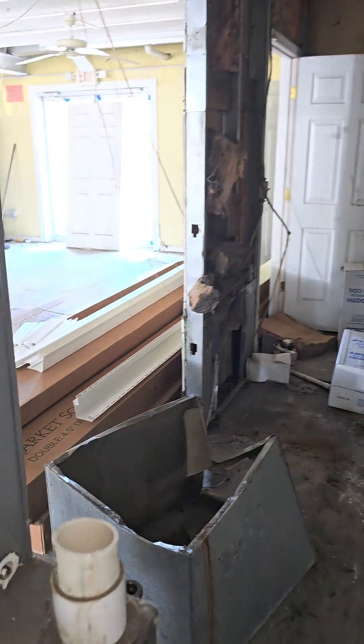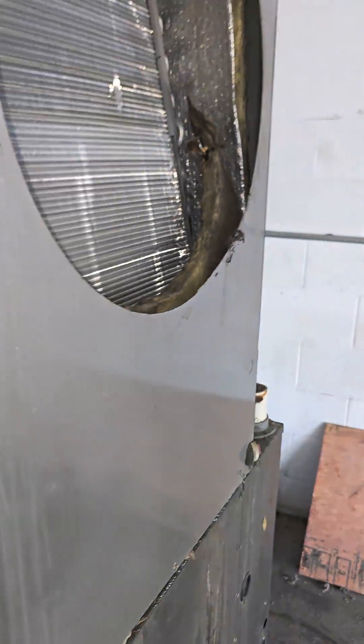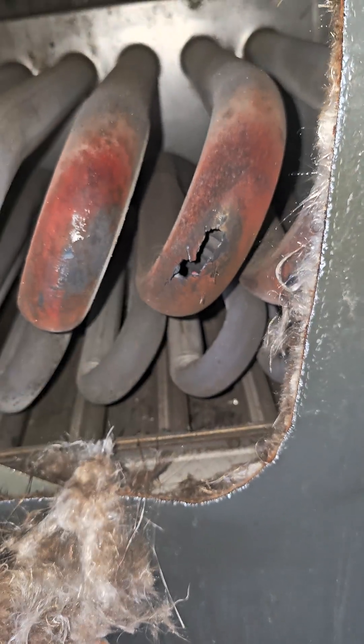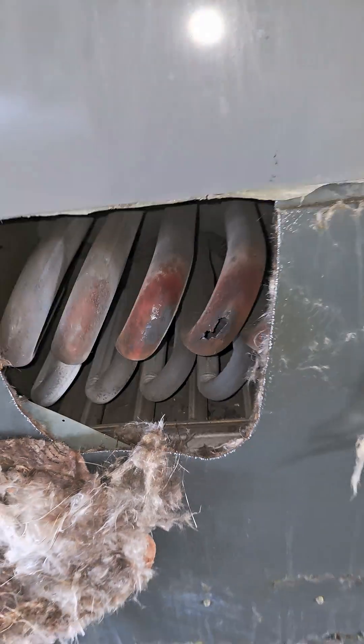Number one, lack of airflow killed the compressor. But even scarier — and I cut this back out for dramatic effect — we have a hole that is essentially burned into the back of this heat exchanger on this unit.